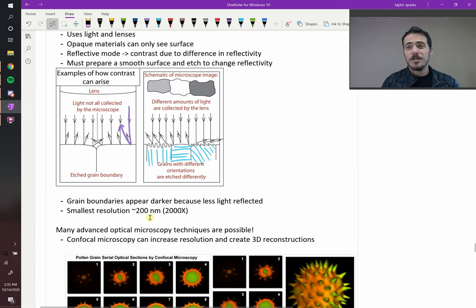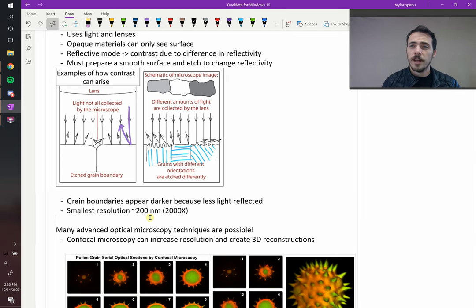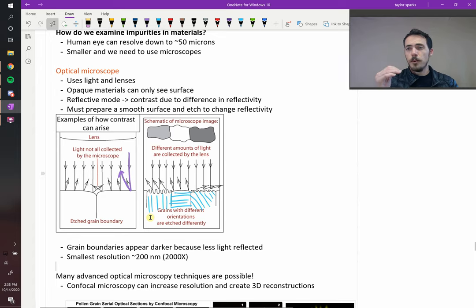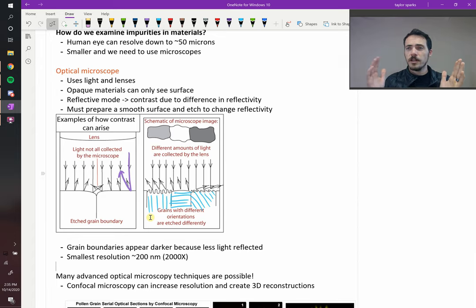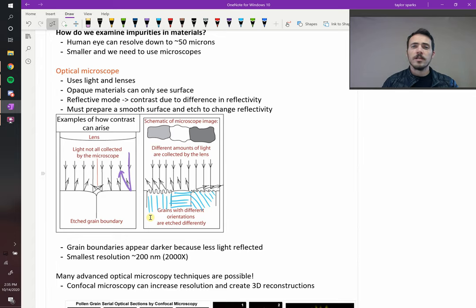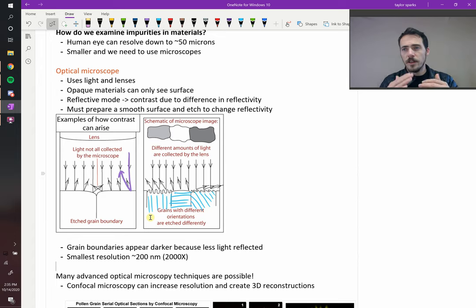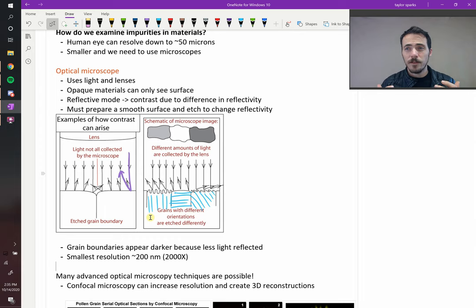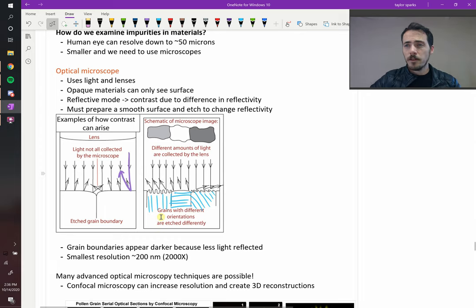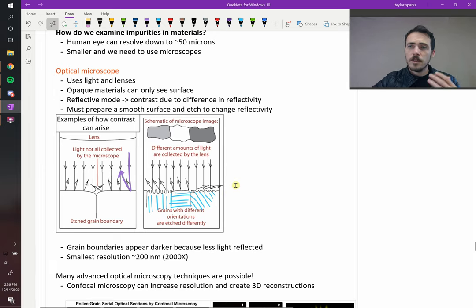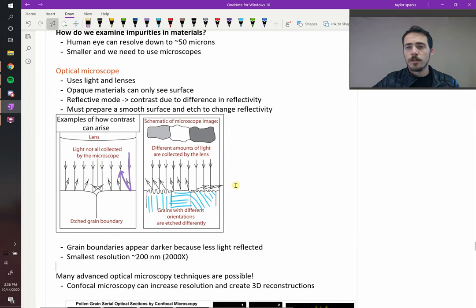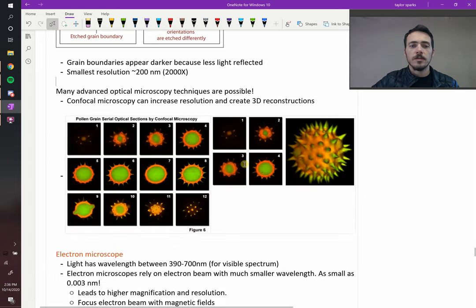The smallest resolution that you're going to be able to get to in optical microscopy is, and this is really pushing it, something like 2000x. That's going to be somewhere around 200 nanometers. And even then, you have to start playing tricks because you have to use shorter and shorter and shorter wavelength light. At some point, your eyeball can't see it anymore. We can only see from like 300 to 700 nanometers or so. So you can't go much smaller than that. But you can start changing what's called the numeric aperture. They'll do tricks where they'll mount the sample in oil because then the index of refraction changes. But really, if you're trying to go smaller, like if you're getting into the nanometer regime, optical microscopy is not the tool. Optical microscopy is good for the micron size things. Looking at bacteria and things like that, those are micron size, you can see them really well. Looking at most microstructures, this is a good tool. But when you want to get to the nanostructure or the crystal structure, optical microscopy won't do it for you. You have to do something else.